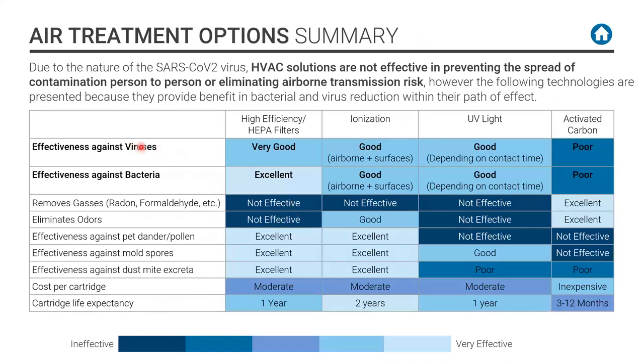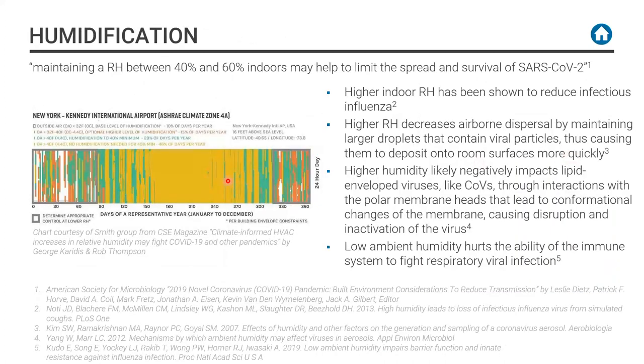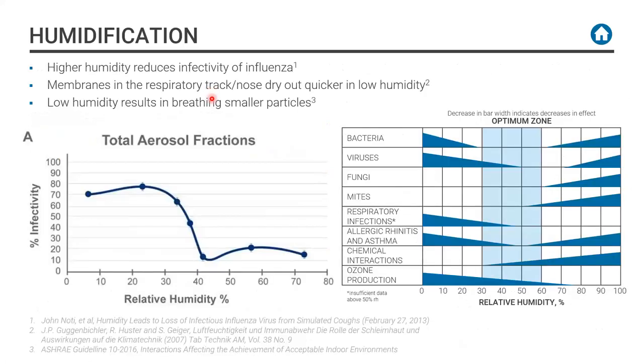So, to summarize the air treatment options, the question is always, what is it you're trying to remove? Our recommendation is always to go to the best filter you can, a MERV 13 or 14 if you can. Ionization we would not recommend for viruses because it has not been peer reviewed. You may want to use it if you're interested in molds and spores in the space. UV lights are good, but it depends on contact time, and carbon filters are really there for odor control. Let's talk about humidification. Maintaining 40 to 60% RH may limit the spread and survival of the virus. I'll just go to the next slide.